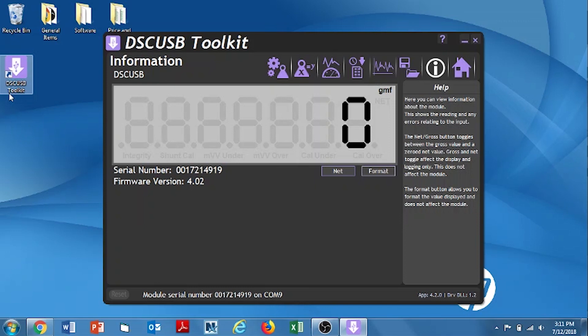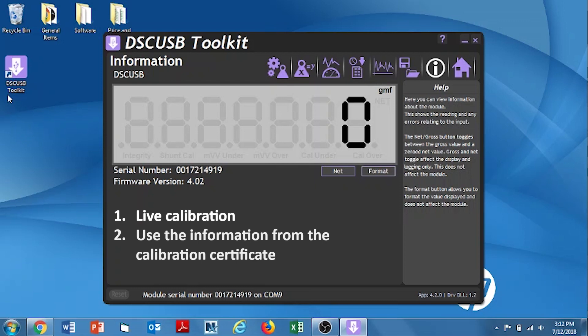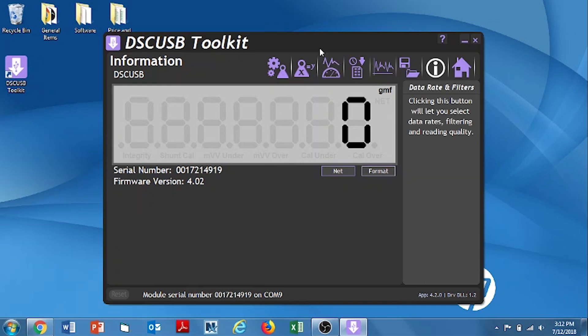For those of you who purchased the unit and did not have an interface calibration, we're going to show you two different methods that you can use to do a calibration on this unit. One is going to be a live calibration where we use an actual weight to do the cal. The second one will be one where we actually just use the information from the calibration cert to perform a calibration. So, on the first method, the live cal, we're going to go into the calibration icon. It looks like a weight.